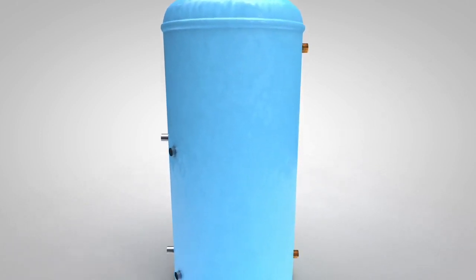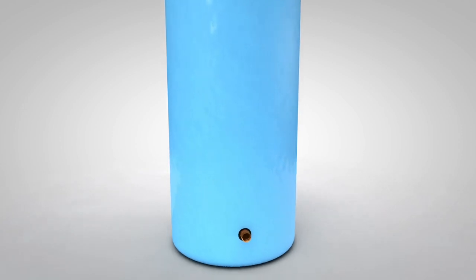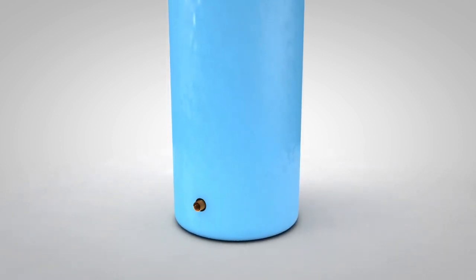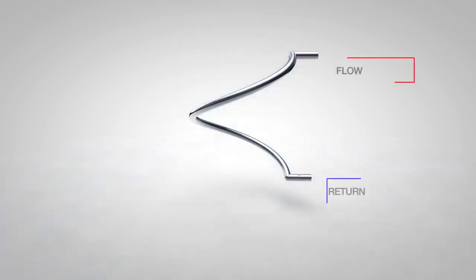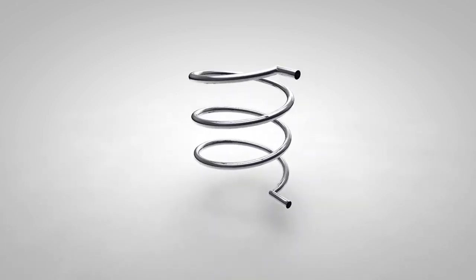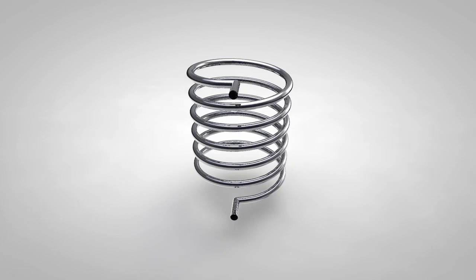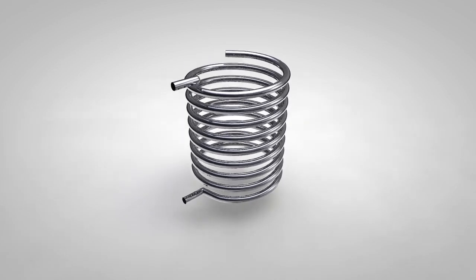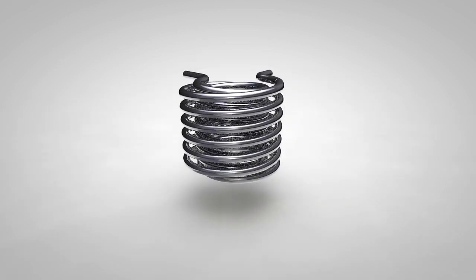First, the coil in its most basic form is made of a simple pipe with one helix turn and joined to two Boss connections, one at each end. This connects to the flow and return of the heat source, usually a boiler. The kilowatt rating of the coil can be changed by increasing or decreasing its surface area. The more surface area, the greater the heat transfer is, the higher the kilowatt rating.